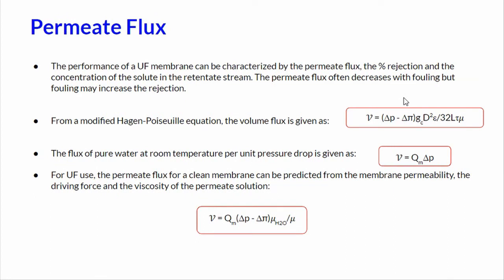Regarding the permeate flux, for a clean membrane, the water is assumed to pass through small pores of the selective layer by laminar flow where the driving force is the pressure difference Δp minus the difference in osmotic pressures across the membrane, that is Δπ. From the Hagen-Poiseuille equation, the volume flux is given as the first equation. The flux of pure water at room temperature per unit pressure drop is given as the second equation. Since it is difficult to get the independent measurements of ε, d, τ, and l for use here, the corrective can be taken through the membrane permeability qm.